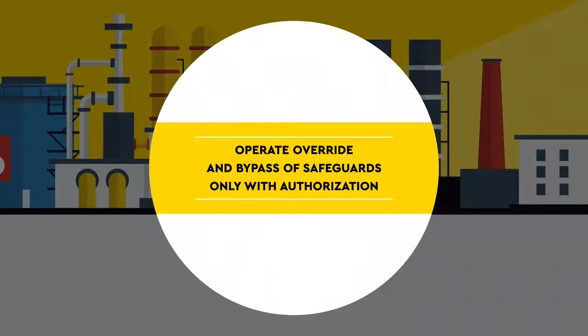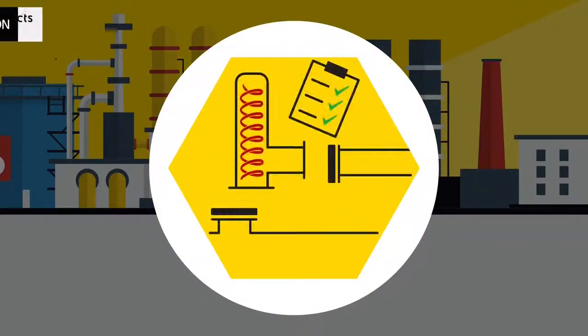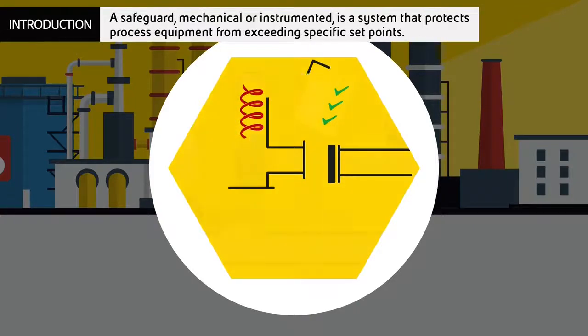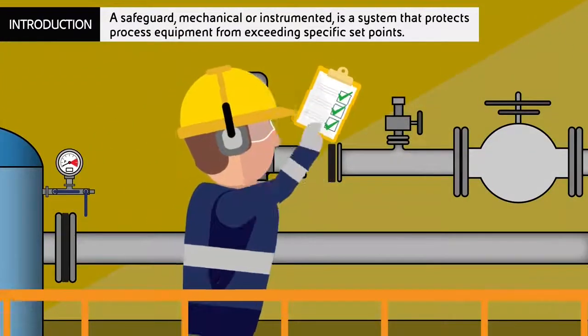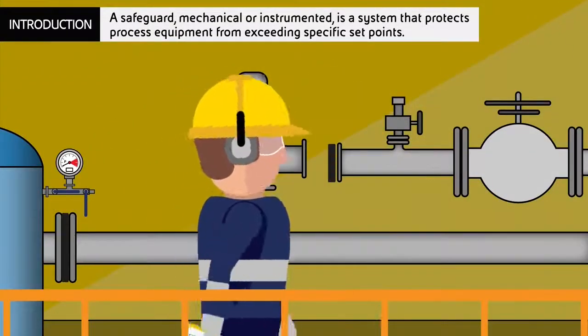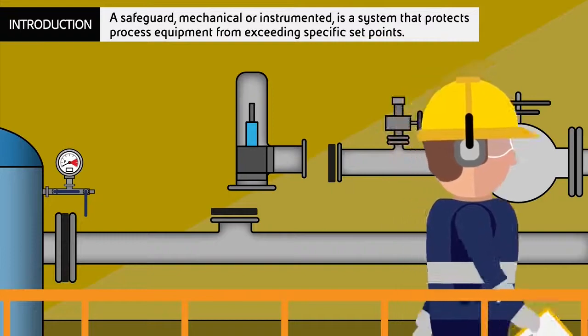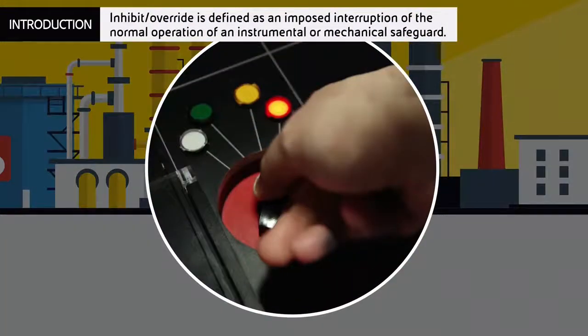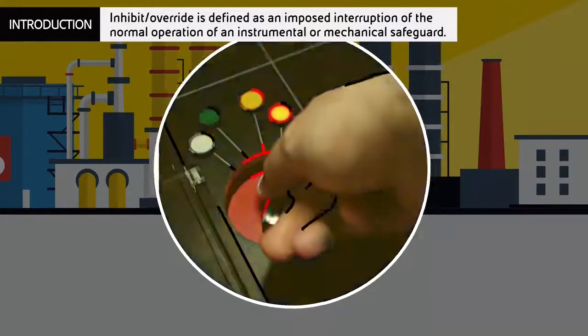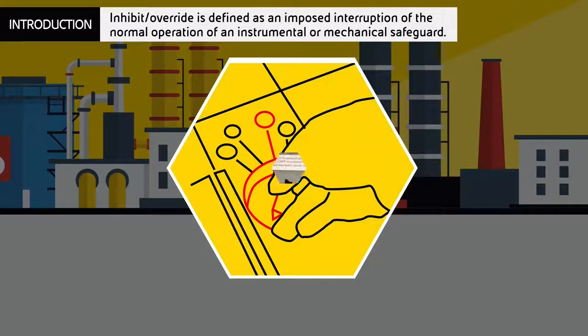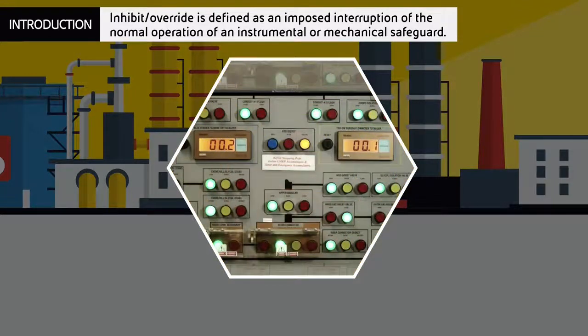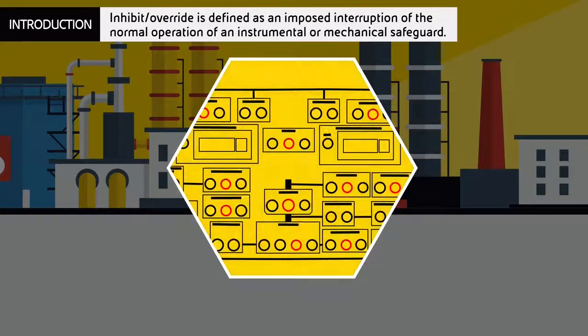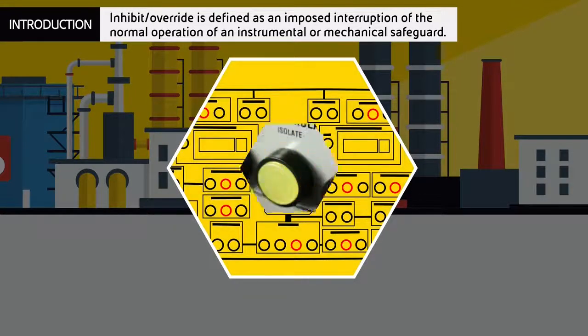Operate override and bypass of safeguards only with authorization. A safeguard, mechanical or instrumented, is a system that protects process equipment from exceeding specific set points. Inhibit override is defined as an imposed interruption of the normal operation of an instrumental or mechanical safeguard.